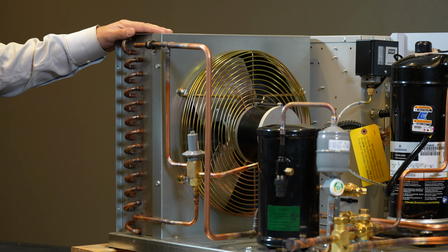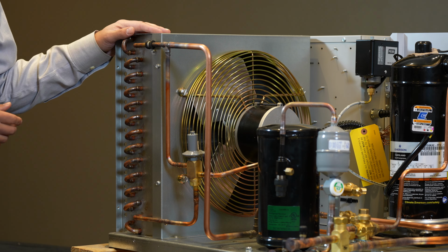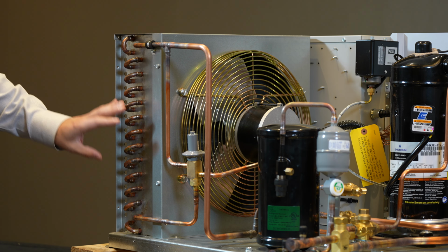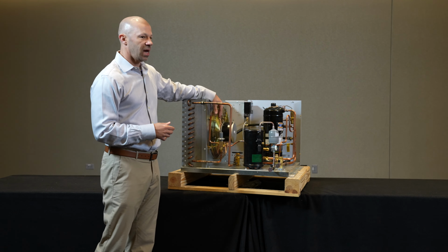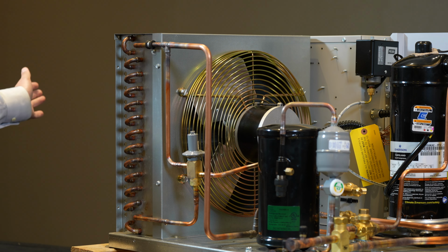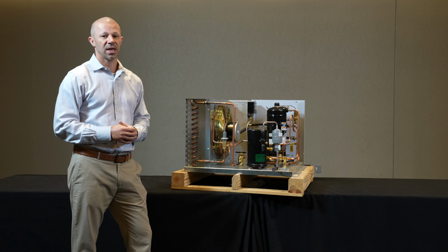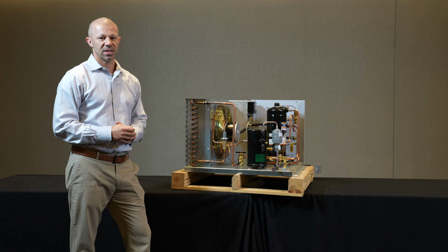This surface is our heat of rejection of the refrigeration system, and we do it by applying a cooling medium to this coil. So what that means is, in this case, this is an air-cooled condenser, where we have a fan motor flowing air over our condenser coil, which is removing the heat from our refrigerant. Another type you might see that's not seen here is a water-cooled coil. But the function of the condenser is the same.